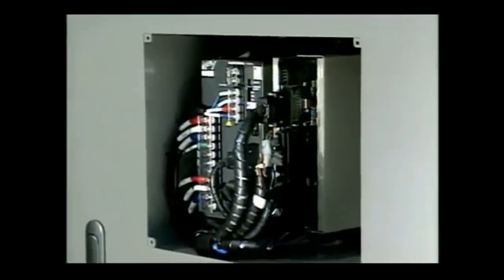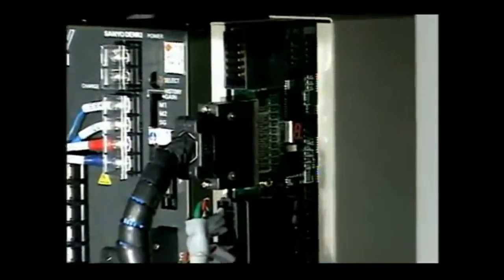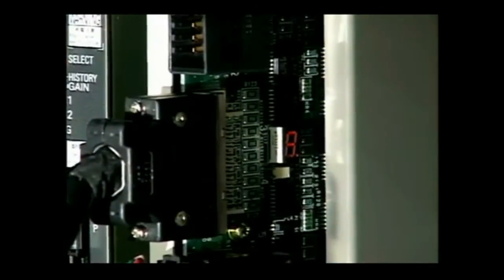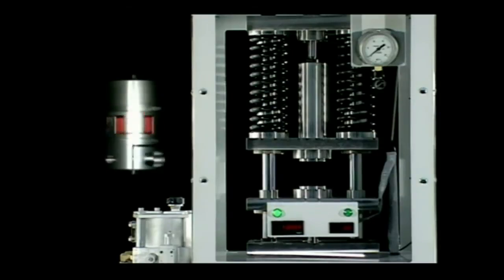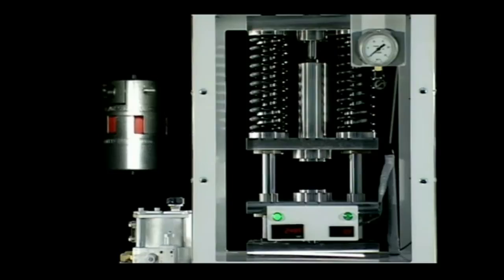The second feature is high precision. The pressure sensor and stroke sensor signals are fed back to a special purpose hydraulic fluid servo controller, and by controlling the pump rotation speed, position can be controlled on the micron level, and operation can be controlled at any desired speed.